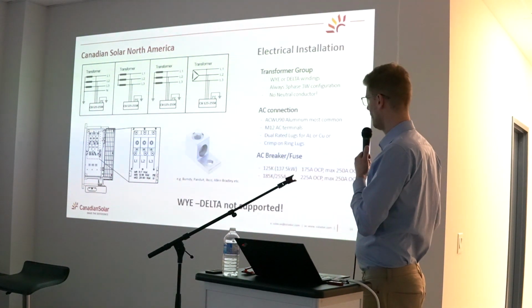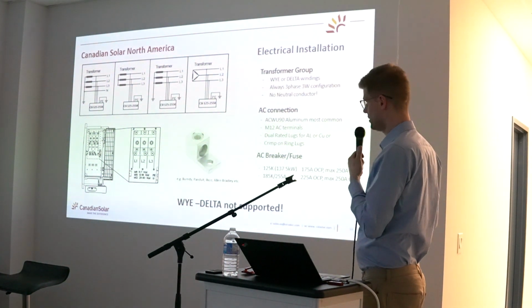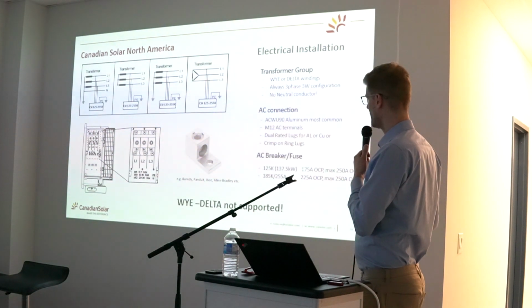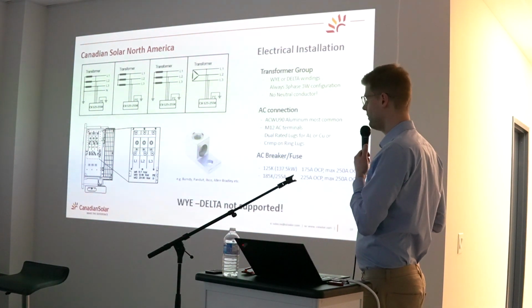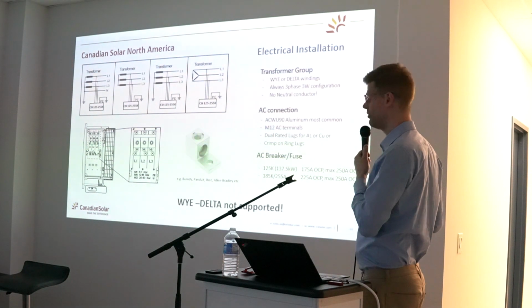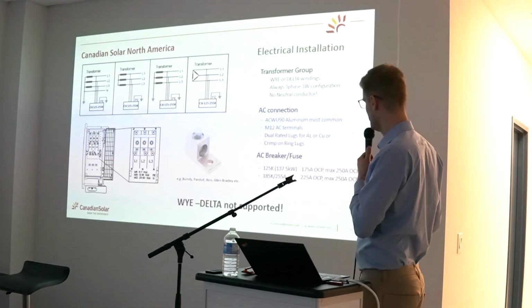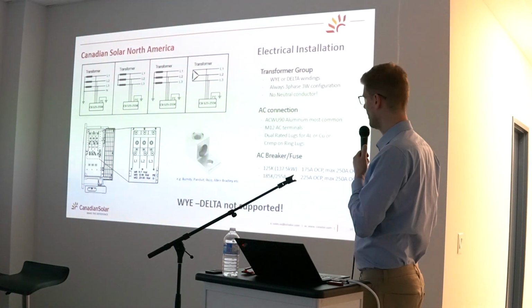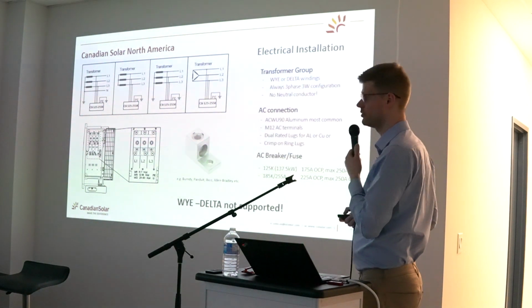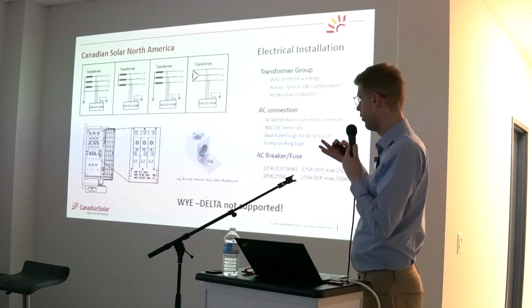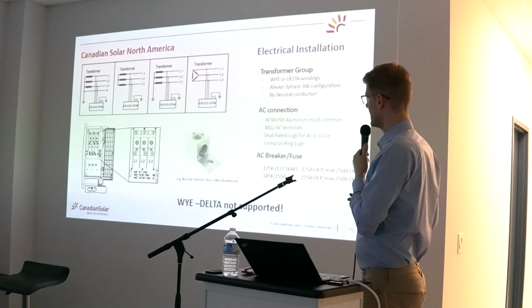Overcurrent protection for the smaller unit, the 125K, which is the 137 kilowatts, is typically a 175 amp overcurrent protection. It can go all the way up for all 3 units to 250 amps. And for the 185 and the 255, it would be a 225 fuse or breaker size.